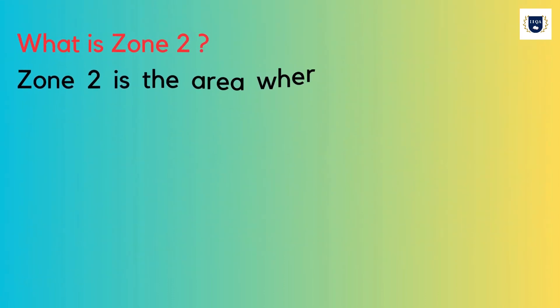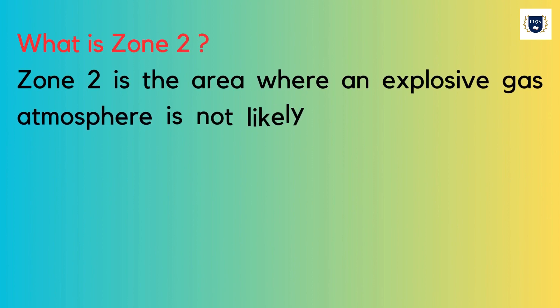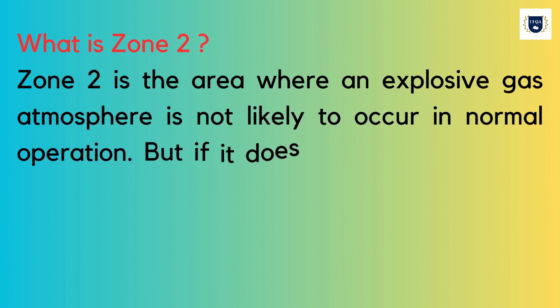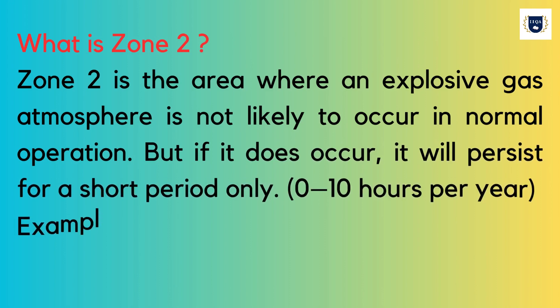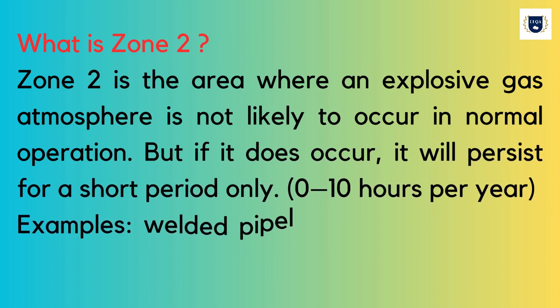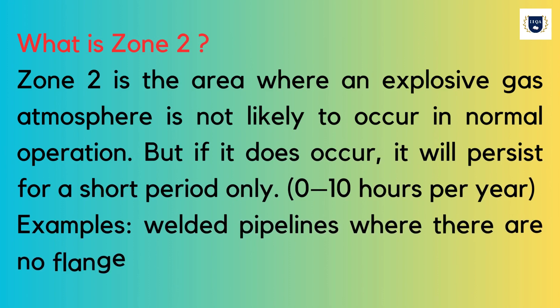What is Zone 2? Zone 2 is the area where an explosive gas atmosphere is not likely to occur in normal operation, but if it does occur, it will persist for a short period only — 0 to 10 hours per year. Examples include welded pipelines where there are no flange joints.